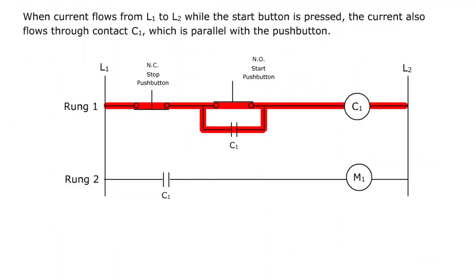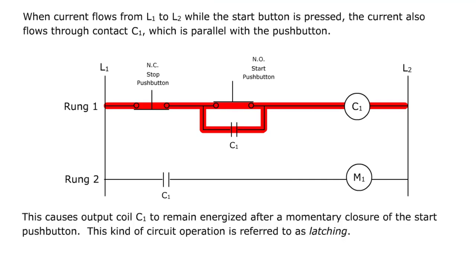When current flows from L1 to L2 while the start button is pressed, the current also flows through contact C1, which is parallel with the pushbutton. This causes output coil C1 to remain energized after a momentary closure of the start pushbutton. This kind of circuit operation is referred to as latching.